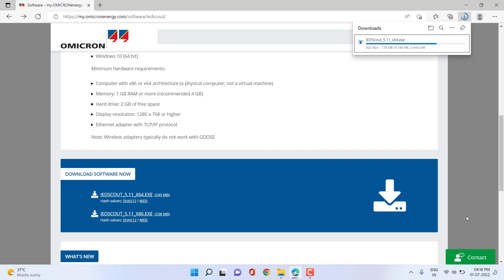After importing an SCL file, you can explore the GOOSE control blocks, report control blocks, and different datasets configured for your different IEDs or applications. You can also get insights about the IED data model for the SCL file imported into IEDScout. You can move the IED from the browser section to the simulator section and even simulate IEDs on your PC without connecting anywhere in the network, in order to learn at a top level.